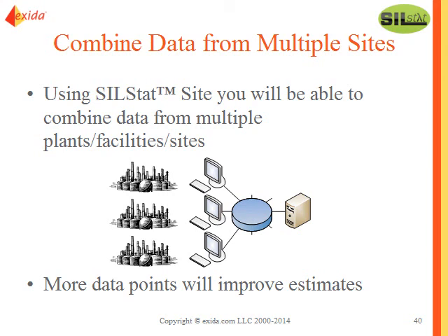Of course, the more data points you have, the narrower your confidence limits are going to be on the estimates of failure rate and demand rate. So that's an advantage you have when you have multiple sites, that you can combine it into basically one data repository.